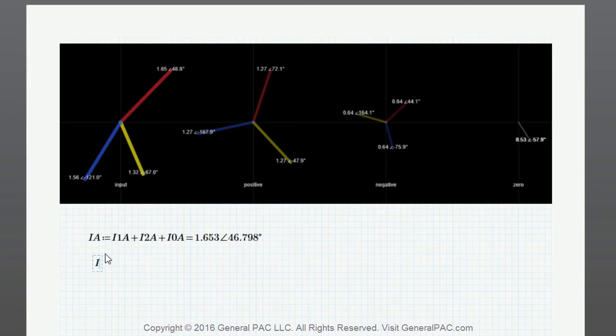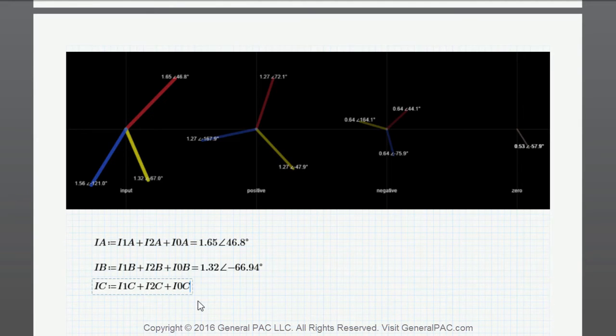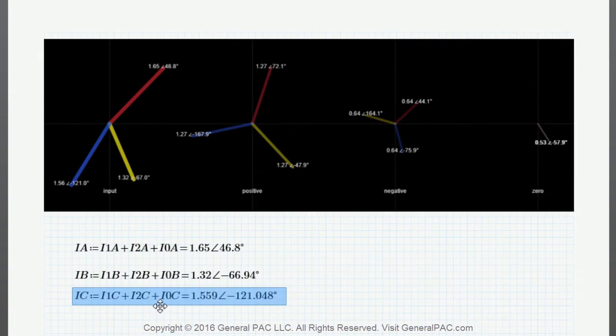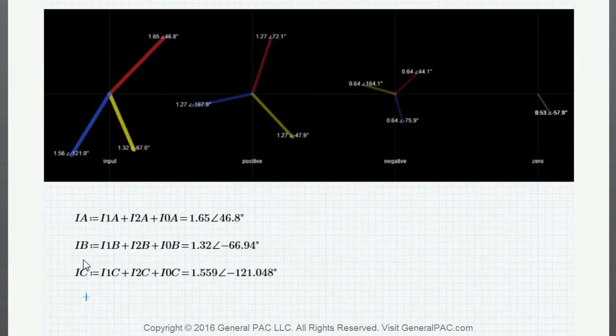Now let's do IB. IB is equal to the positive sequence component for phase B plus the negative sequence component for phase B plus the zero sequence component for phase B. And there you have it: 1.32 at negative 67 degrees, which matches our original yellow phasor. For phase C, the original phasor is equal to positive sequence plus negative sequence plus zero sequence component of phase C, and that equals 1.56 at negative 121 degrees — matching our original system phasor.